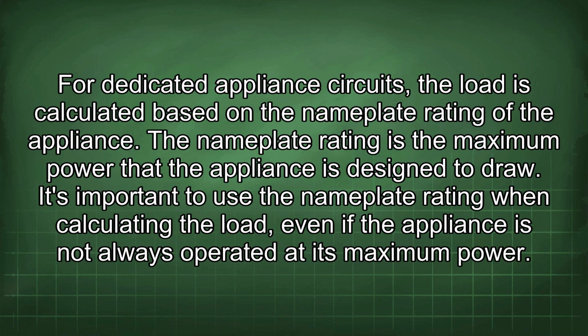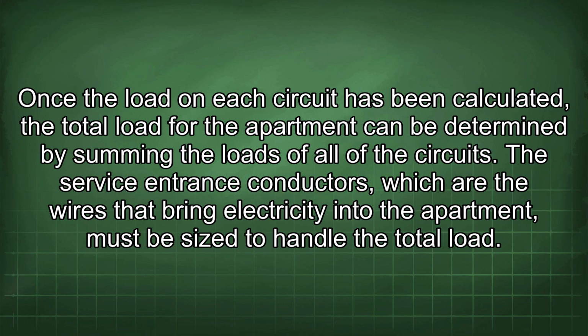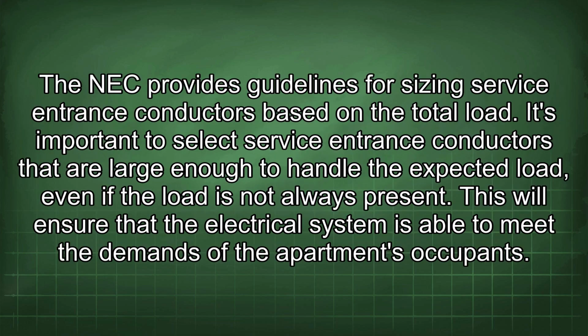It's important to use the nameplate rating when calculating the load, even if the appliance is not always operated at its maximum power. Once the load on each circuit has been calculated, the total load for the apartment can be determined by summing the loads of all of the circuits. The service entrance conductors, which are the wires that bring electricity into the apartment, must be sized to handle the total load. The NEC provides guidelines for sizing service entrance conductors based on the total load. It's important to select service entrance conductors that are large enough to handle the expected load, even if the load is not always present.